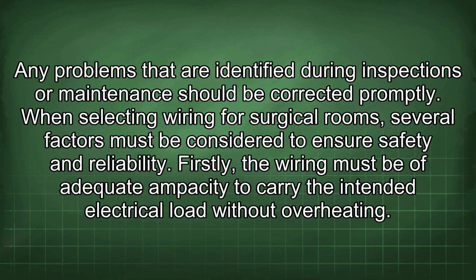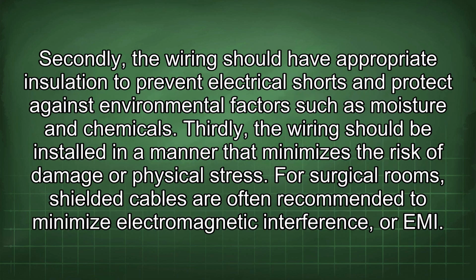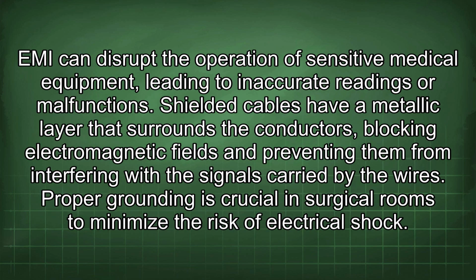When selecting wiring for surgical rooms, several factors must be considered to ensure safety and reliability. Firstly, the wiring must be of adequate ampacity to carry the intended electrical load without overheating. Secondly, the wiring should have appropriate insulation to prevent electrical shorts and protect against environmental factors such as moisture and chemicals. Thirdly, the wiring should be installed in a manner that minimizes the risk of damage or physical stress. For surgical rooms, shielded cables are often recommended to minimize electromagnetic interference, or EMI. EMI can disrupt the operation of sensitive medical equipment, leading to inaccurate readings or malfunctions. Shielded cables have a metallic layer that surrounds the conductors, blocking electromagnetic fields and preventing them from interfering with the signals carried by the wires.